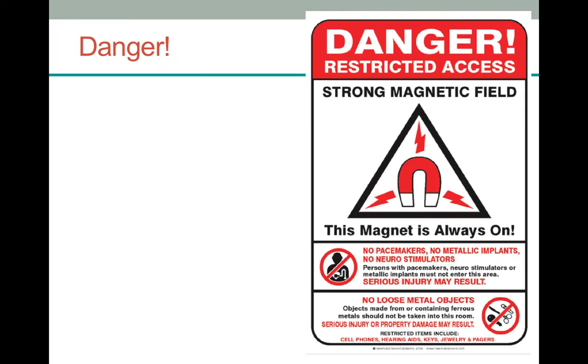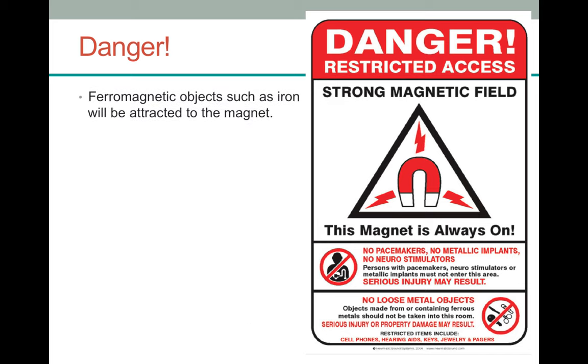But this strong magnetic field poses a real danger. Certain materials with ferromagnetic properties, such as iron, will be attracted into the magnet. Hazardous items that we would not want people to take into the scanning room include belts, phones, clips, laptops, and fire extinguishers.